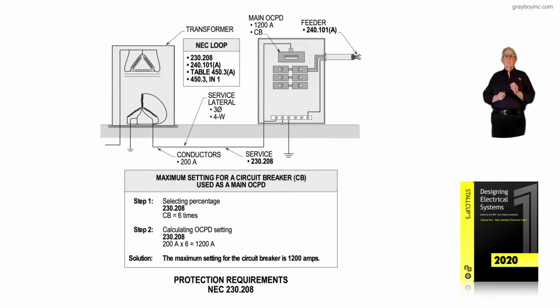Notice in the NEC loop, we say before starting to design or install this type of installation, be sure to review 230.208, 240.101A, and where transformers are involved, review 450.3 Informational Note 1 and Table 450.3A, which deals with systems over 1,000 volts. And for protection, we are referenced to 240.100 and 240.101.